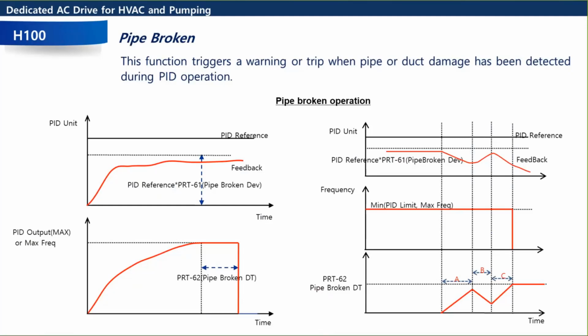If you're running PID, and let's say you have a 60 psi set point, but your feedback is down at 20 or 30 psi, and then your motor is running 60 hertz. It's running full speed because it's trying to get up to that 60 psi reference. If we're looking at this table here, our feedback is really far off from our reference. So you have this line right here. This is your detection level. If there's a large difference between your set point and your feedback, you have a delay time, just like everything else. You hit those criteria, and then you could trip out, or you could do a warning, because there may be a broken pipe. There may be a valve that's open that shouldn't be open, and you're just spraying water all over. So there's a problem. That's the purpose of the broken pipe detection.